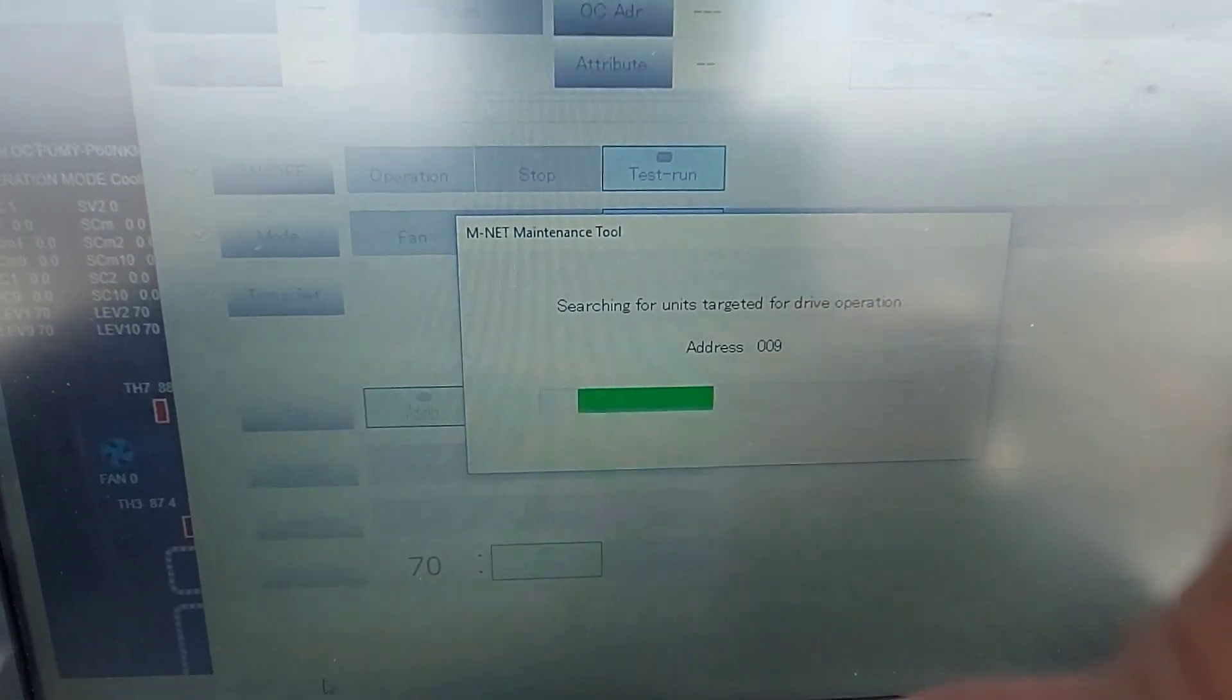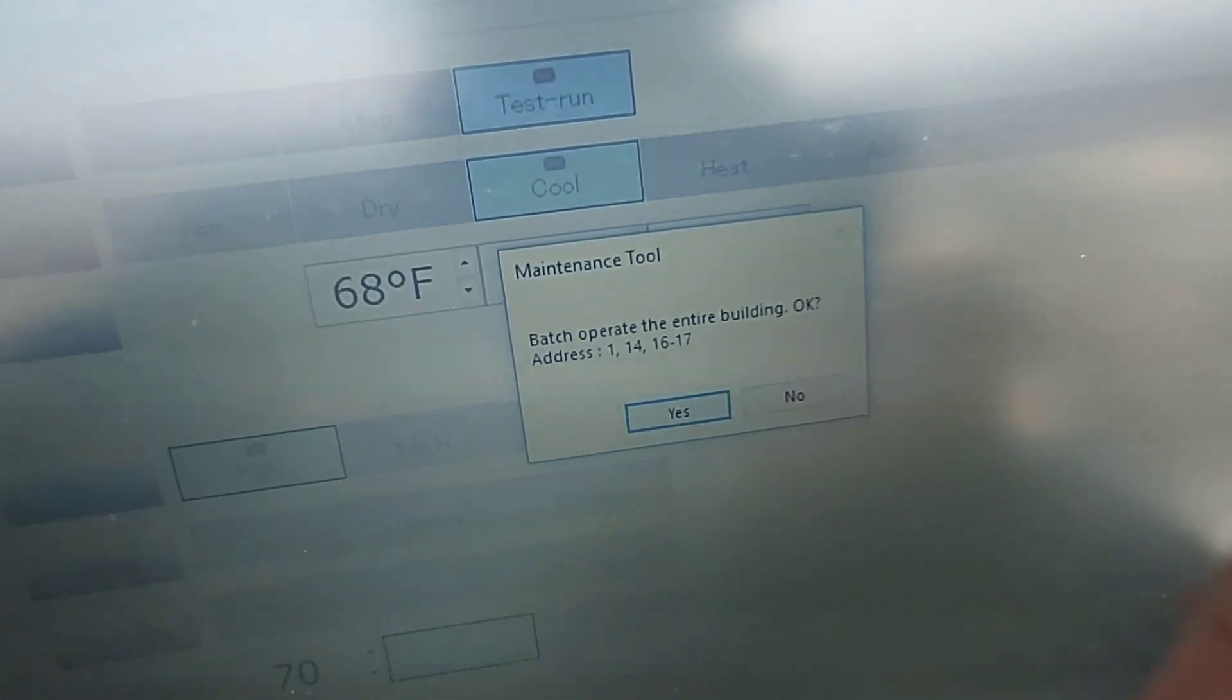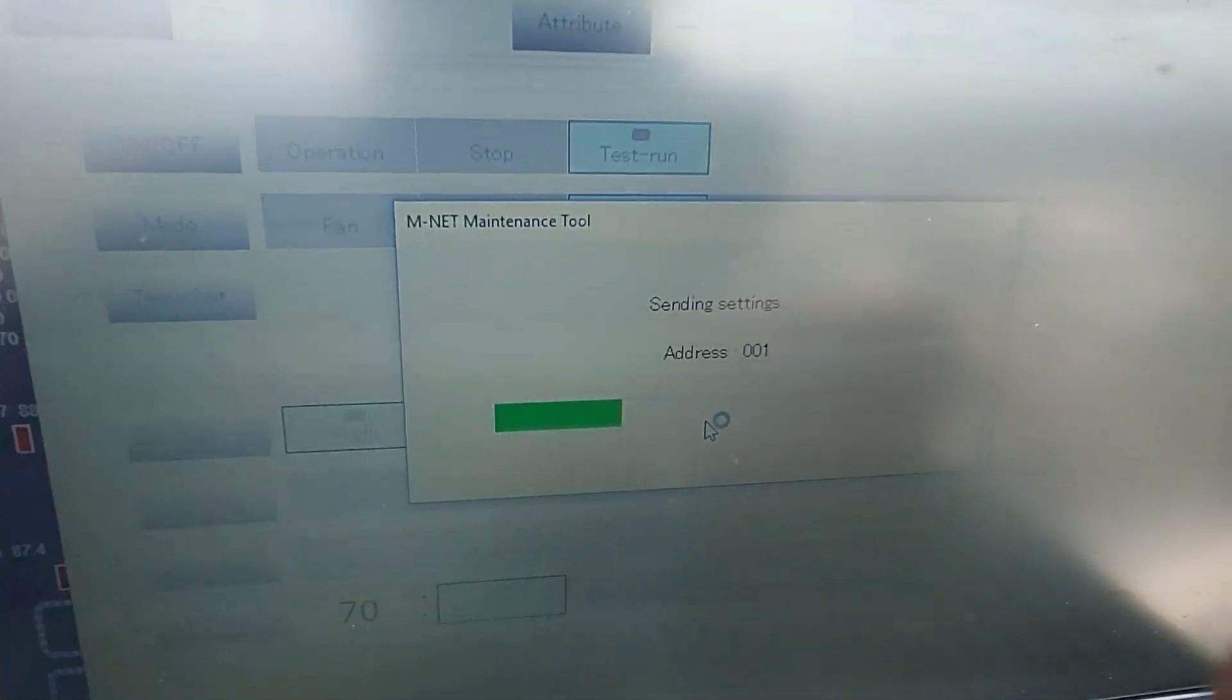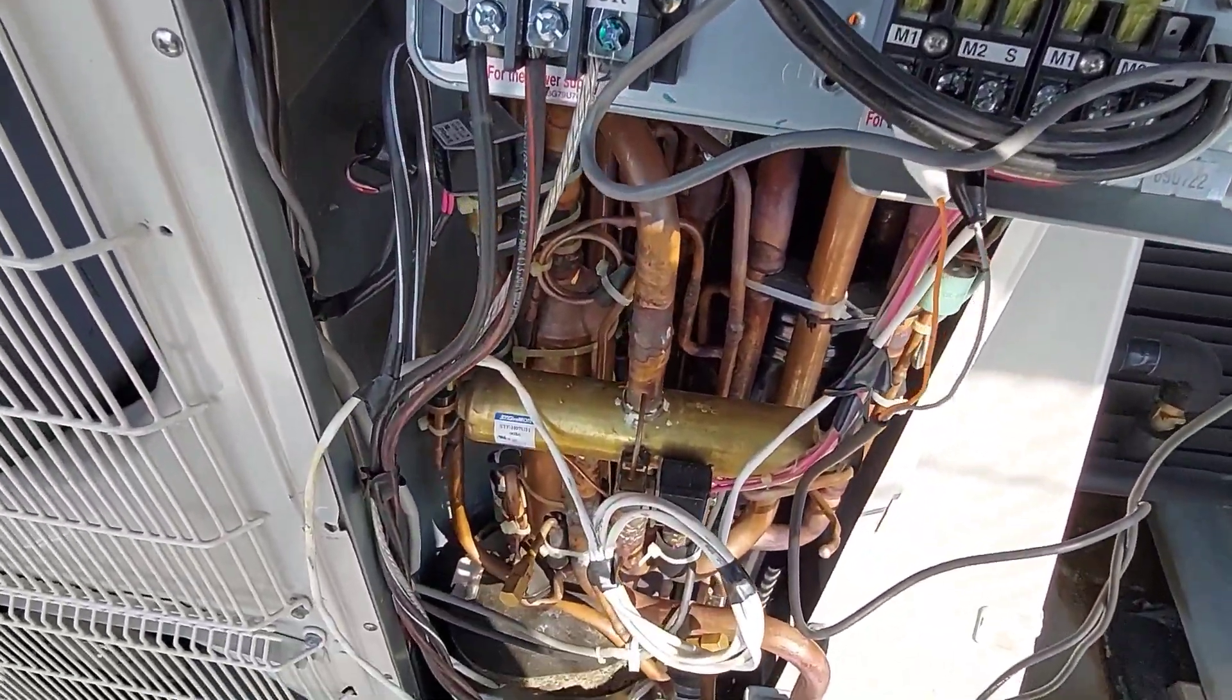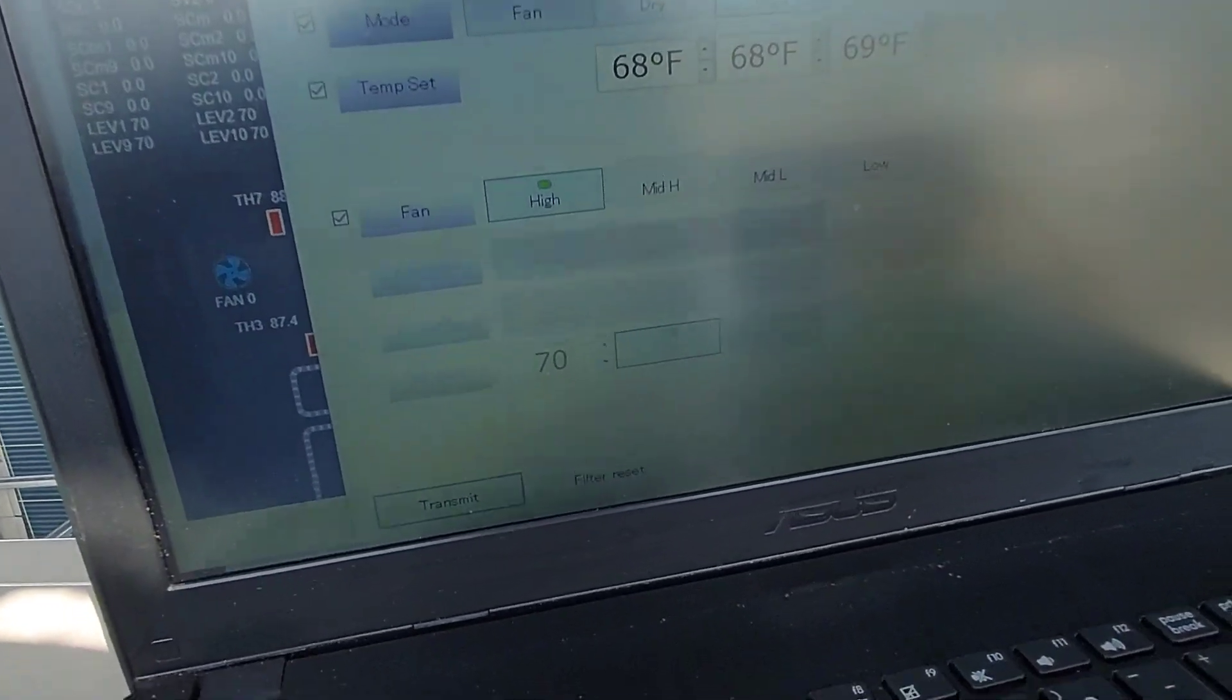It's going to scan all the addresses and then ask if you want to do that. Now if this works the machine will start up right away, you hear the clicks. So it's checking all the addresses, it's going to apply the settings. Once it's done it asks you do you want to do that to all the indoor units, yes I got four units. So now it's applying the settings. Typically you'd hear the clicks and I don't even hear clicks so I'm assuming this thing will not start. This thing is locked in error, it won't start. It says completed and yeah nothing happens.